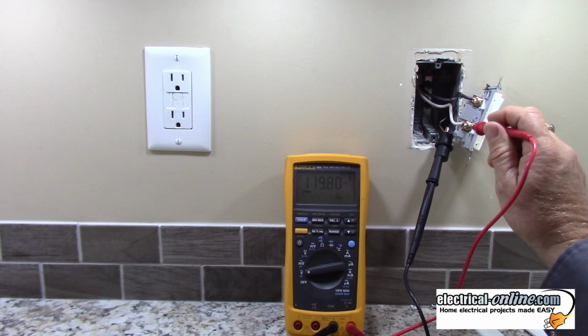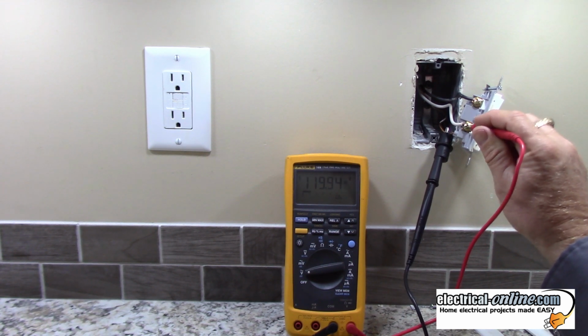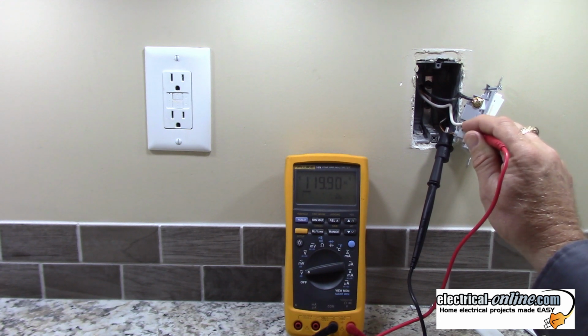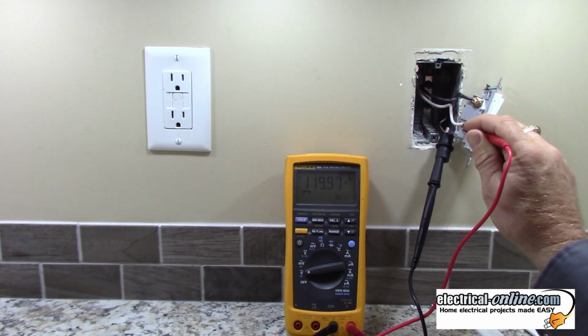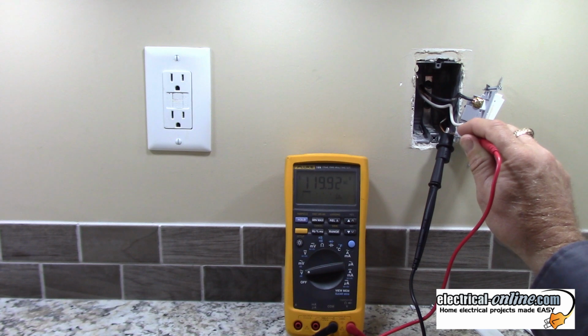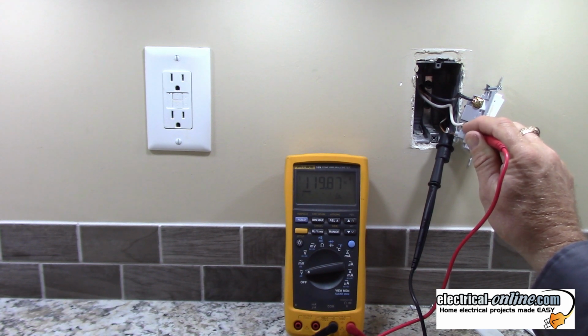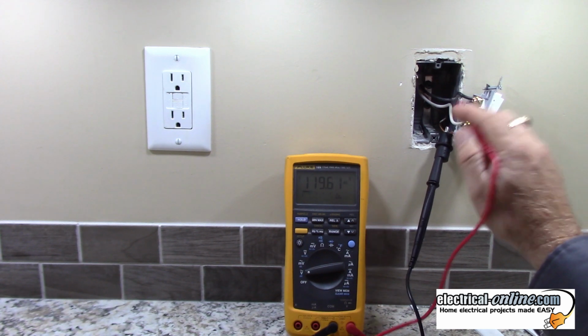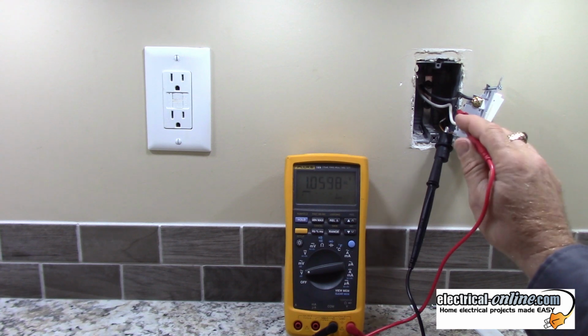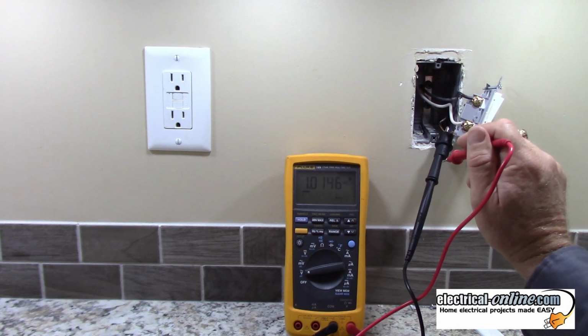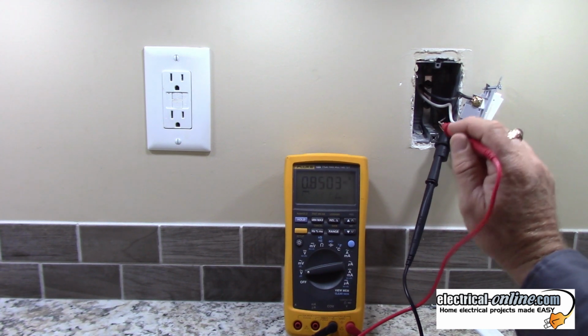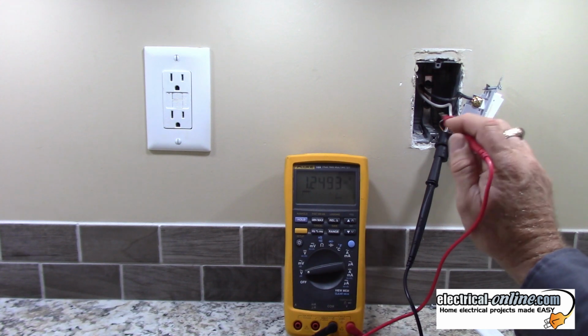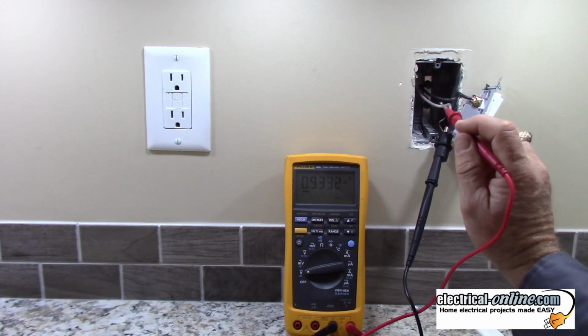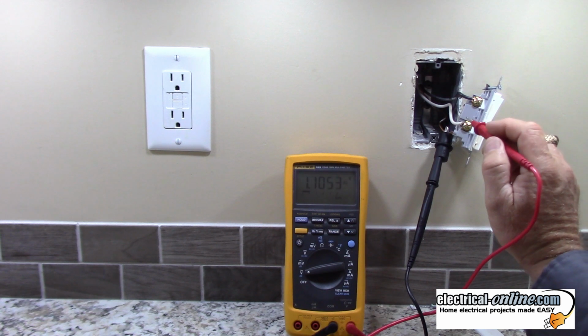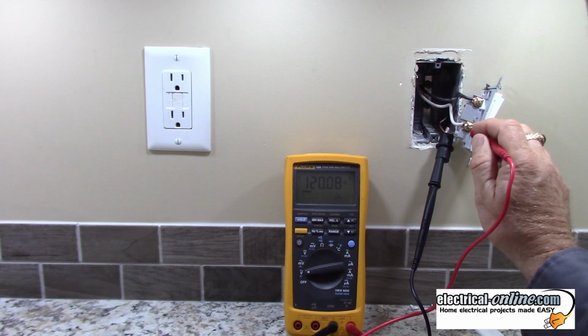This is a switch that just is a switch leg drop, which incidentally is no longer allowed to just use the white wire as a hot like this, but this house was wired before the code changed. So that wire should be marked as black, and I see the electricians that did this didn't do that. So we're going to do that before we're done. We're going to take a black felt pen and color that white wire in because it's used as a hot here, but that's off topic. Let's just check. And we have 120 volts on that terminal.